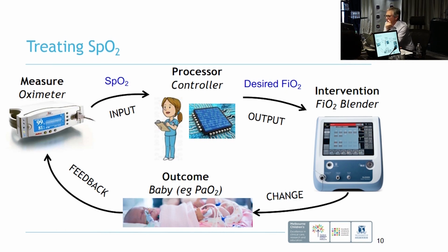And currently that's generally done by a member of healthcare staff, so a nurse or a respiratory therapist or a doctor. But the closed loop oxygen says, well, why don't we change the healthcare staff to a computer chip in a computer in the ventilator, right? And it's very similar to what happens with volume targeted ventilation or volume guarantee. You are handing over the changing of the PIP to the ventilator instead of you and your nursing staff.